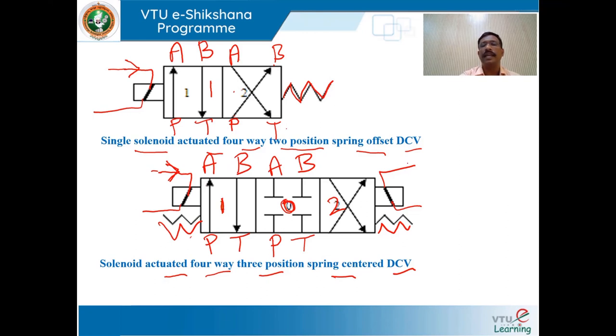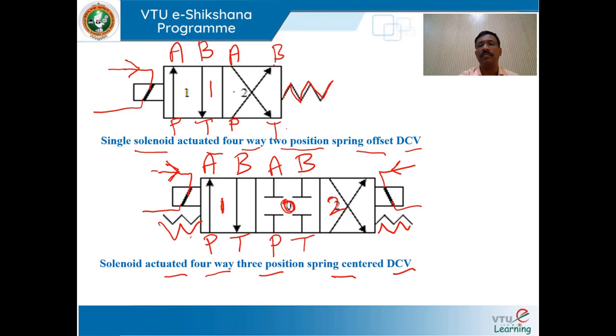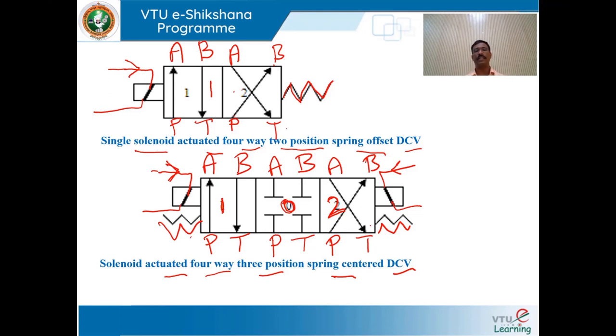When you energize the coil on the other side, the spool slides and shifts to that envelope configuration — P connects with B and A connects with T. This is how to draw a symbol for solenoid actuated four-way three-position spring-centered directional control valve.